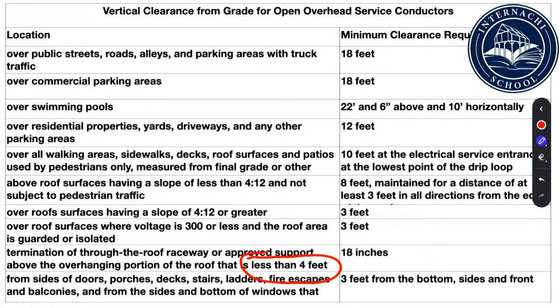Sides, important to catch this word. From the sides of doors, porches, decks, stairs, ladders, fire escapes, and balconies, and from the sides and bottom of windows, that's 3 feet. So you can have these wires going over the top of those windows. That doesn't matter if they're bare. And we're not talking about stuff that's in conduit. We're only talking about the actual wires themselves. All right. But anything else, if it's going left, front, right, below 3 feet of a window, then that's an issue.